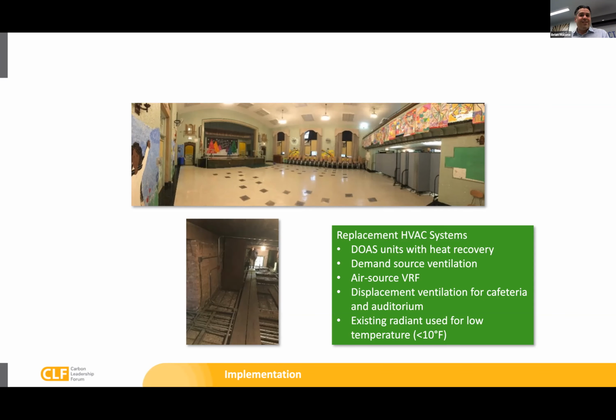...we had to be a little creative, so we designed the air source system being cognizant of what those future upgrades are. So when they are able to replace the windows and add that insulation, the air source system on its own would be able to handle the building down to -10 and below.